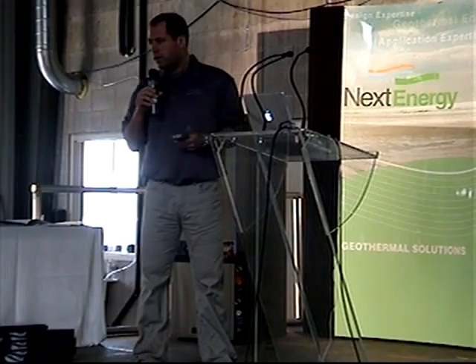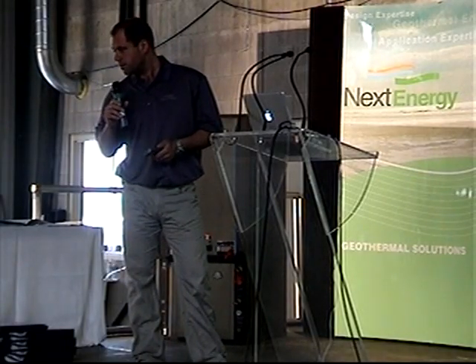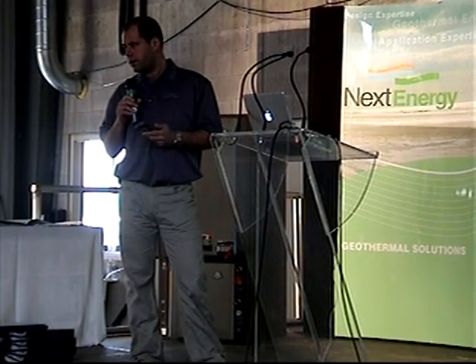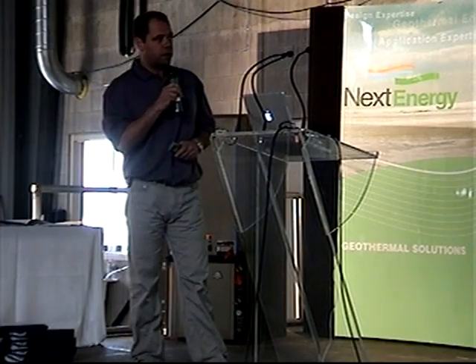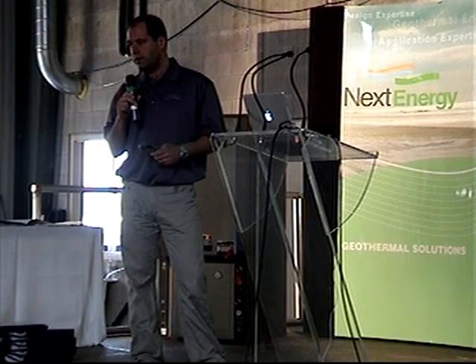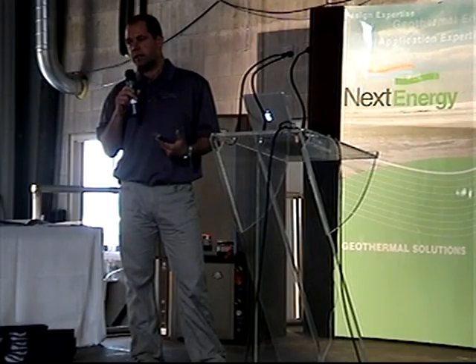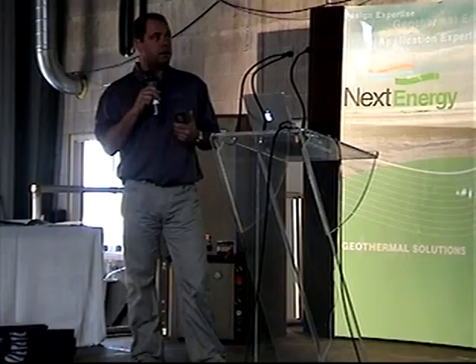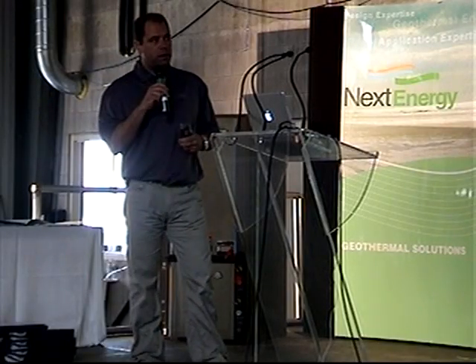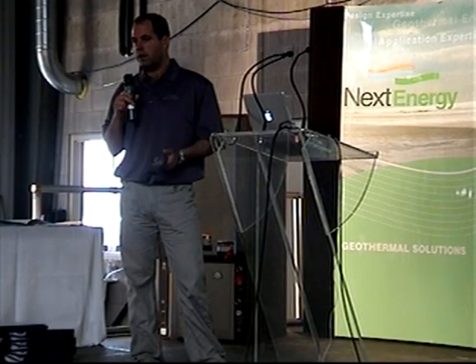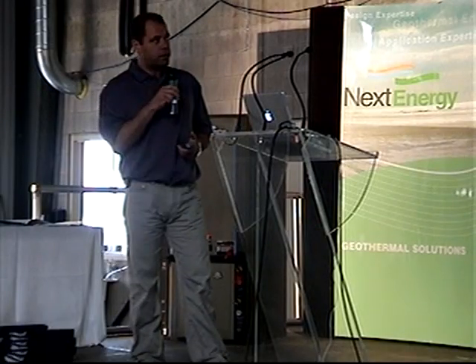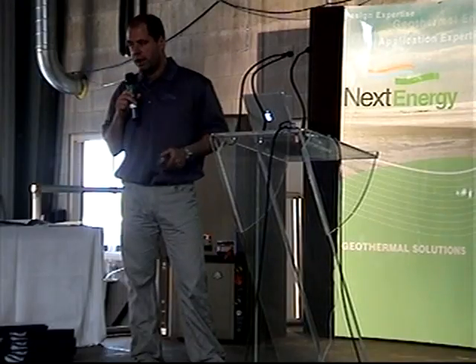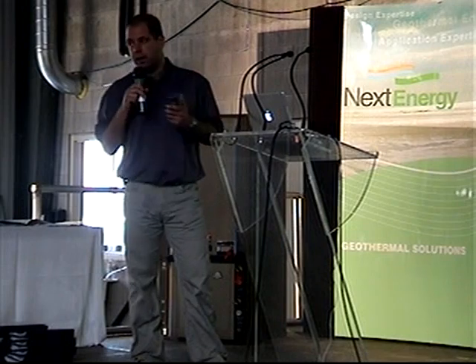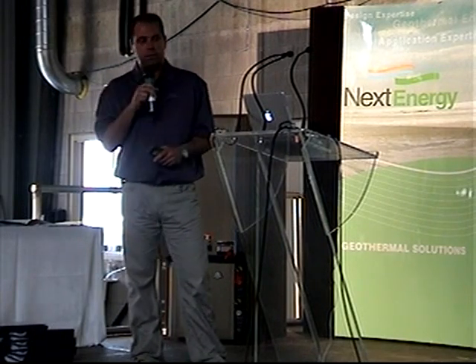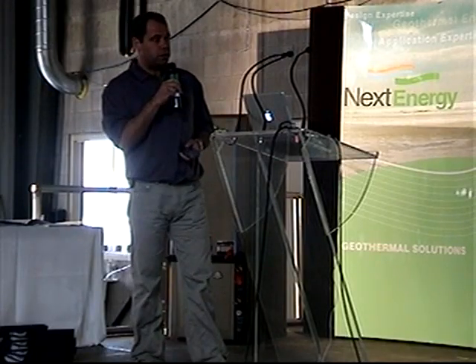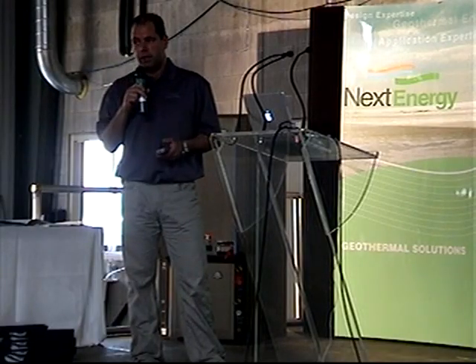Okay. Did you guys get the handouts, those forms? What those forms are for is, those are going to be startup procedures now. And what's going to happen is you're going to get that with every heat pump, and you're going to fill in all the pressures, all the temperatures. You're going to send that back, and that's going to trigger your warranty, and it's also going to go into a database, like a spreadsheet we'll have here, and it'll be pulled up based on the serial number. So if you guys call in a year and a half down the road, that same unit's not working properly, I can get the serial number, pull up your startup form that you sent back, and look at all your temperatures and your pressures that you had on startup, and it'll help pinpoint where your problem is and see where something possibly has changed in the unit. And not only that, we know that it worked properly from the beginning, so something has changed.